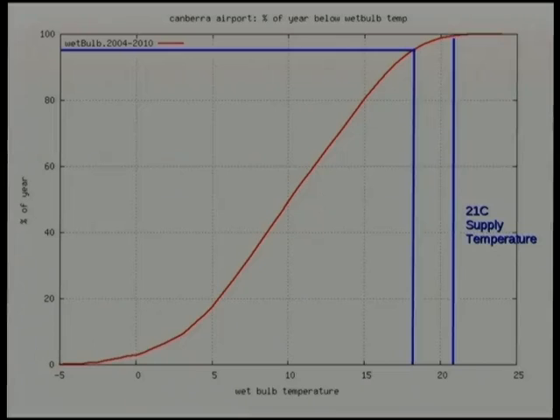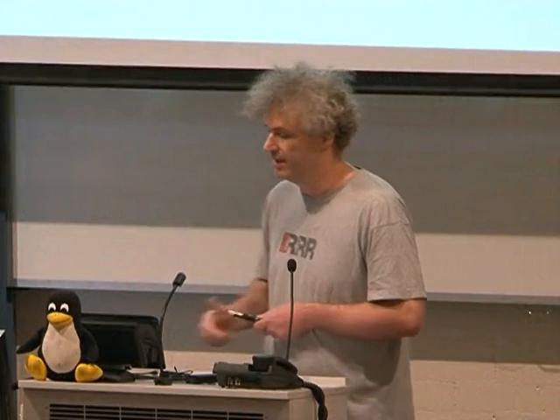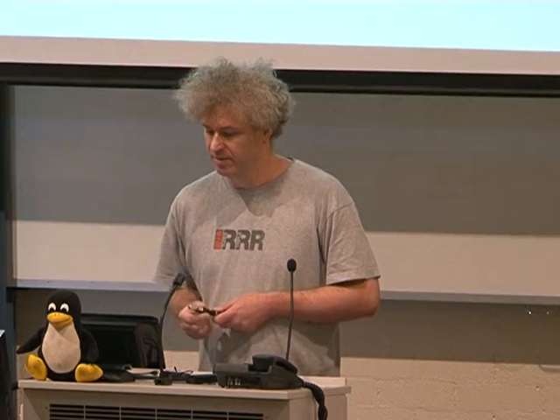This means finding all the hot spots across the equipment and eliminating all the air leaks from all the different containment systems we have in the room. And if we can get the water supply temperature up to 21 degrees and still keep the computer equipment at a reasonable temperature, then in Canberra we can get to about 95% of the year completely free cooling, which is hopeful.